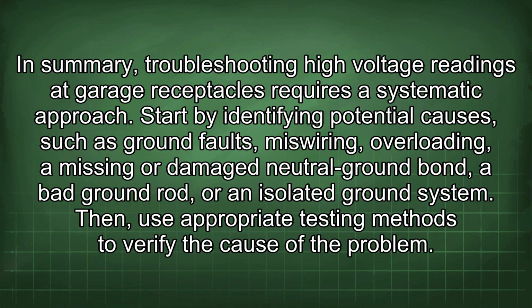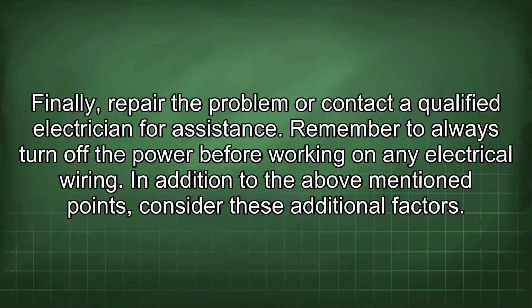In summary, troubleshooting high voltage readings at garage receptacles requires a systematic approach. Start by identifying potential causes, such as ground faults, miswiring, overloading, a missing or damaged neutral ground bond, a bad ground rod, or an isolated ground system. Then, use appropriate testing methods to verify the cause of the problem. Finally, repair the problem or contact a qualified electrician for assistance. Remember to always turn off the power before working on any electrical wiring.